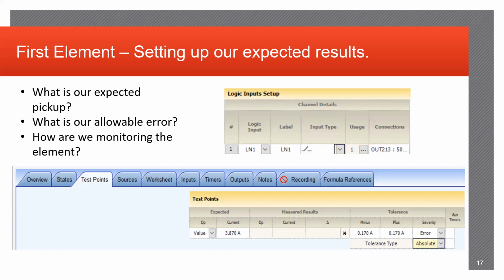So setting up your expected results, this will be, excuse me. Down in this lower box here is going to be what your results bar will look like. It will show you your value for your expected results, the measured results after the test is complete, and the tolerance here is for your sake, especially once you get into more finicky elements. You can actually place a buffer in there if it's not supposed to pick up on the specific value. You can give it somewhat of a buffer, especially when you're getting into, you know, crazy small current values and stuff like that.